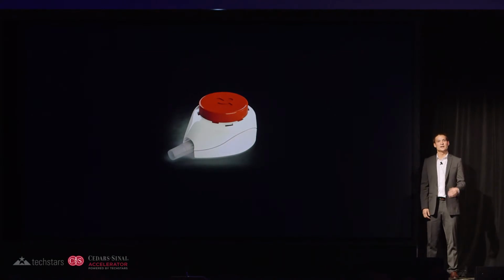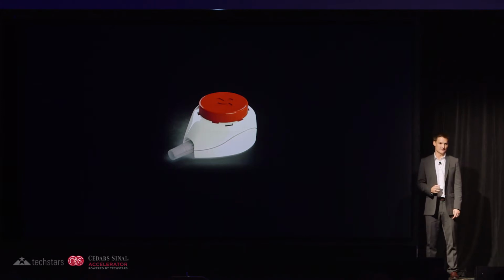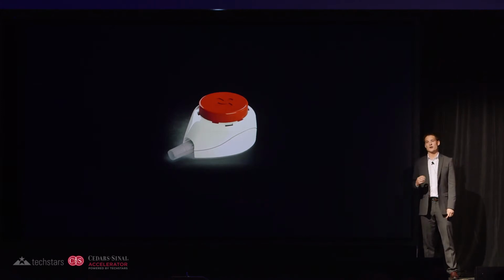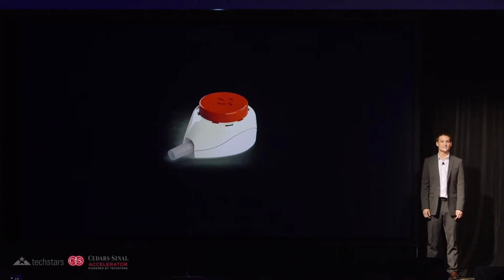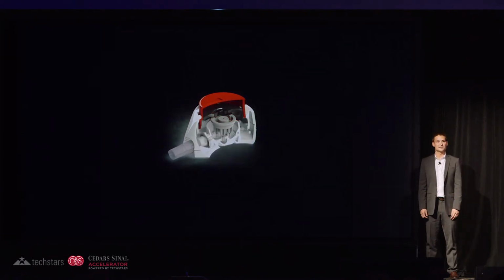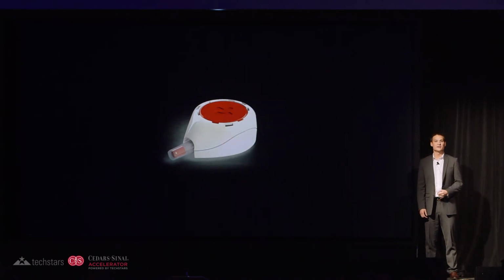The Hemolink is the result of 4 years of development sponsored by DARPA and has 6 patents that protect the technology. We have an issued patent around our approach to microfluidics that allows the Hemolink to be simple, reliable, and cost-effective. We call it suspended microfluidics. When you press that button, 4 small needles come out of the device to make a puncture and are automatically retracted and locked in the device for safety. A small vacuum is generated to enhance the blood collection process. Those microchannels direct the blood into a standard tube that can be used by any clinical lab for testing.